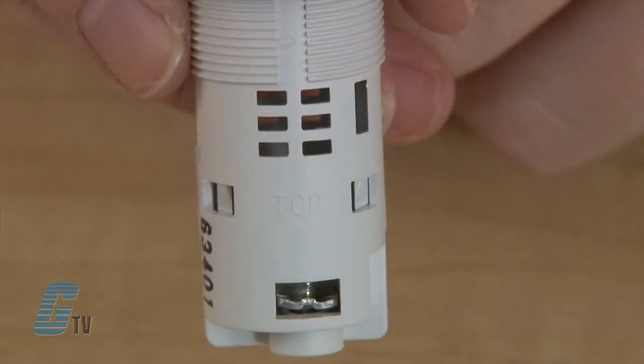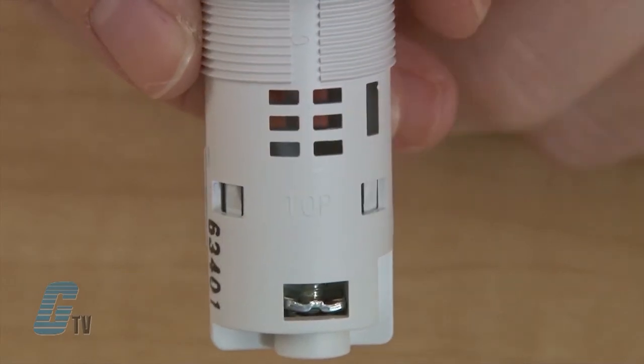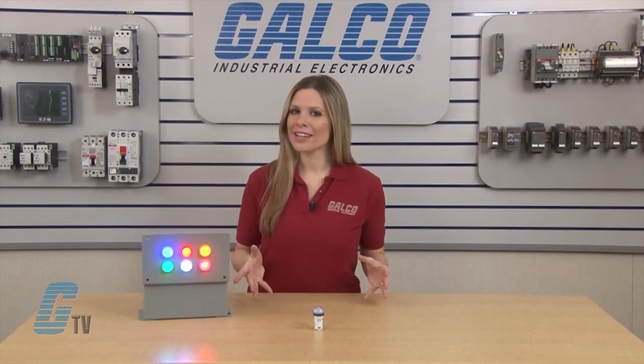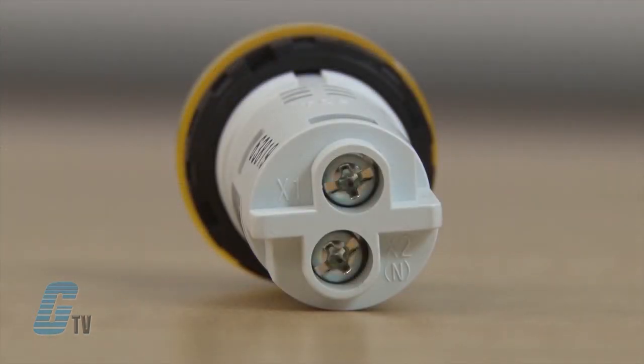The AP22M is easy to install with a visible top marking location and a single locking ring. The gaskets do not need to be removed for installation. The screw terminal wiring connections are ideal for 16 to 14 gauge wire, with the negative pole wired on X2 and the positive on X1.